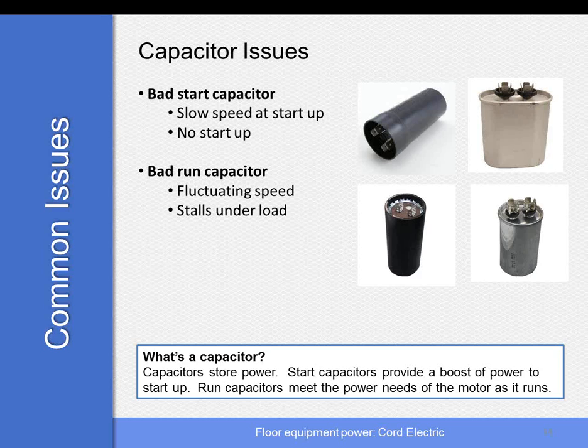Capacitors. A capacitor is a device that stores a charge. Now when they're used in this case, a start capacitor or a run capacitor, a start capacitor will give an extra boost to the machine at startup. Get that motor spinning quickly. A run capacitor will smooth out the variations in the voltage and the amp demands, the current draw demands of the motor as it goes across the floor.